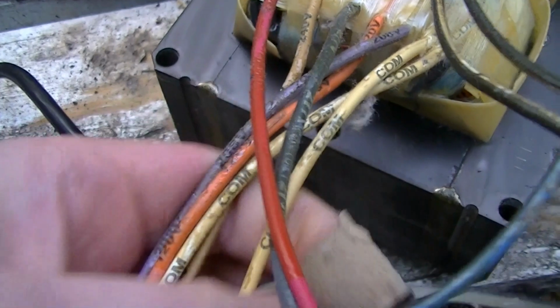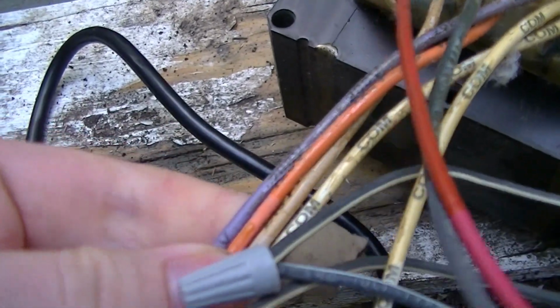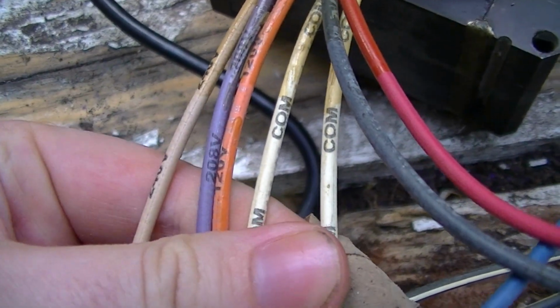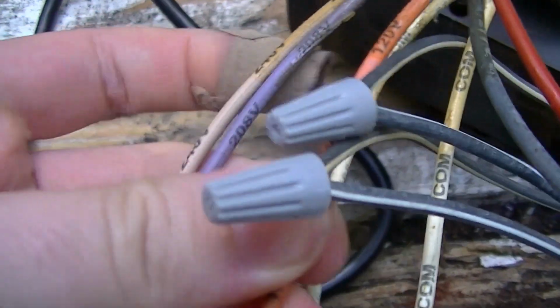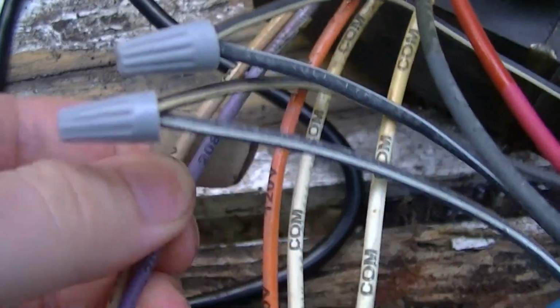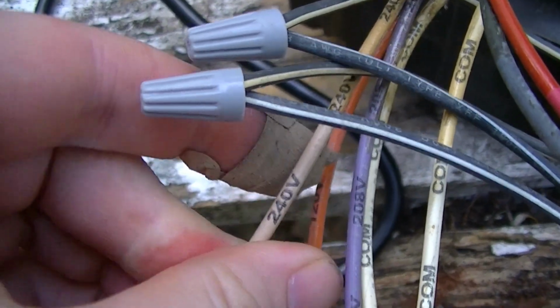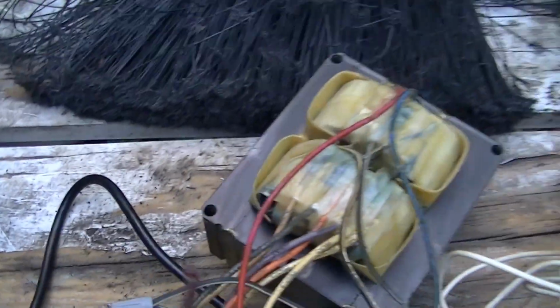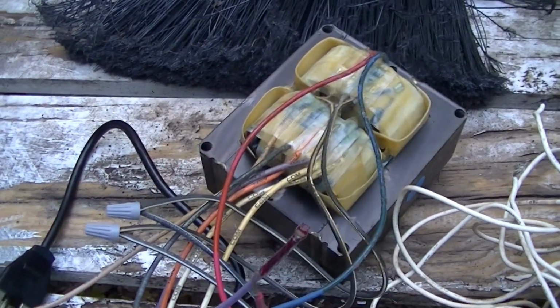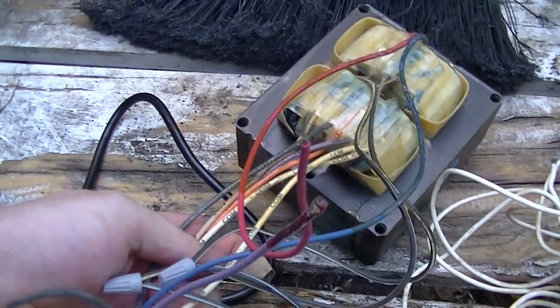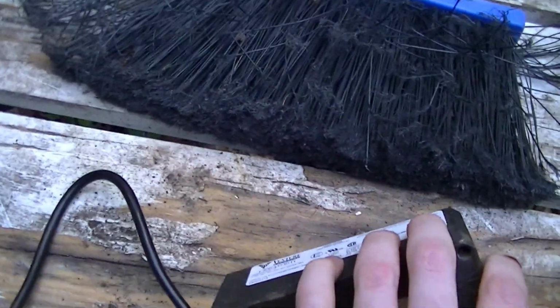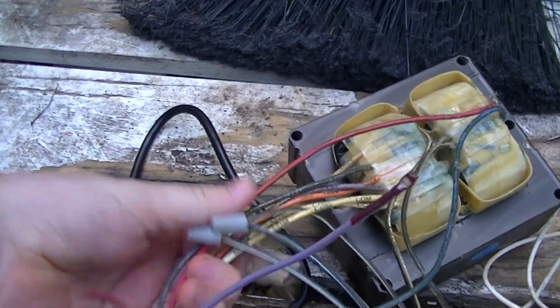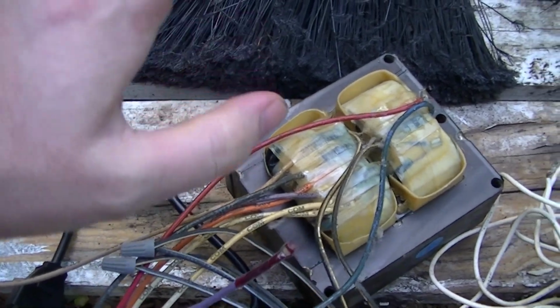I've gone over that in previous videos. But you see the colors of all the various input wires. The common wires are kind of white, off-whitish color. Orange is 120 volts. Purple is 208 volts. Tan is 240 volts. And this unstriped black wire is 277 volts. And this is actually quite a common color code for certain manufacturers. So if you come across one of these ballasts and the label is somewhat damaged, but it has this particular color code, now you know what it is.